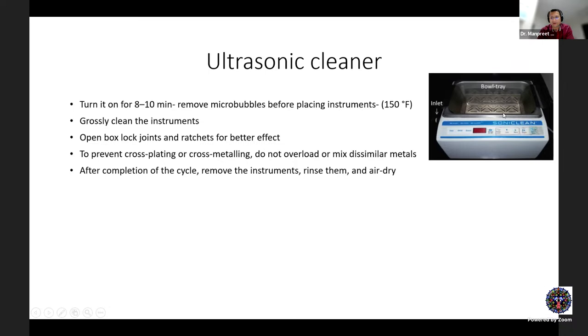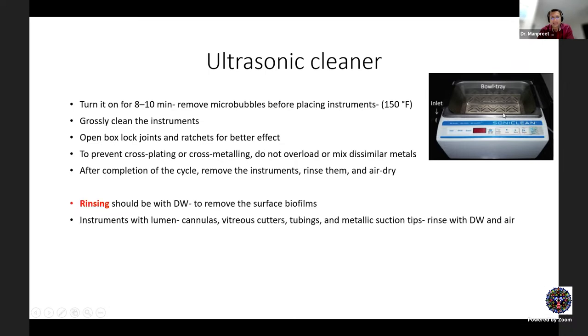After the ultrasonic cycle, remove instruments, rinse with distilled water, and air dry. Instruments with lumens — cannulas, cutters, tubing, metallic suction tips — should be rinsed with distilled water using a 10 or 20 cc syringe, then cleared with high-speed air passed through a small tube to remove water particles from inside the lumen.